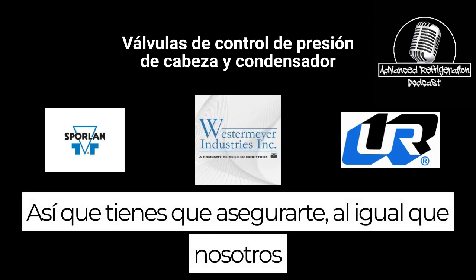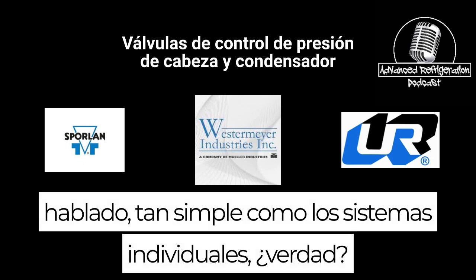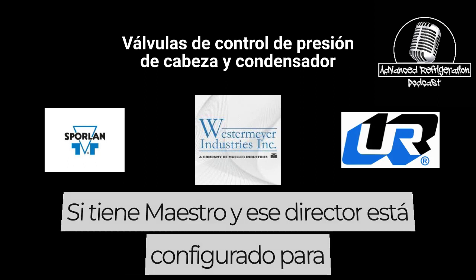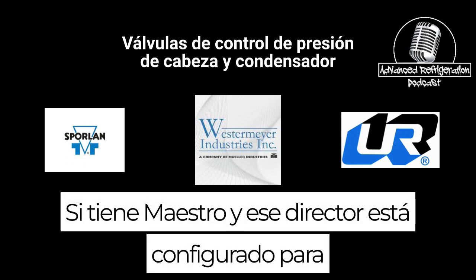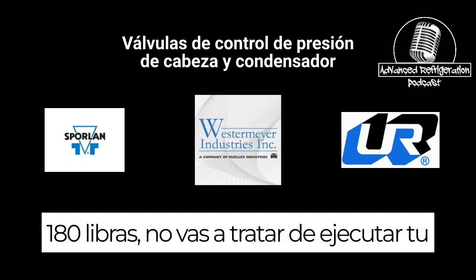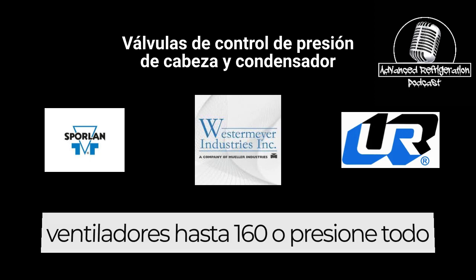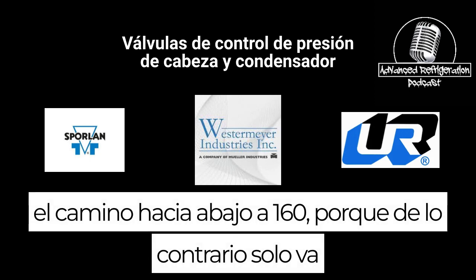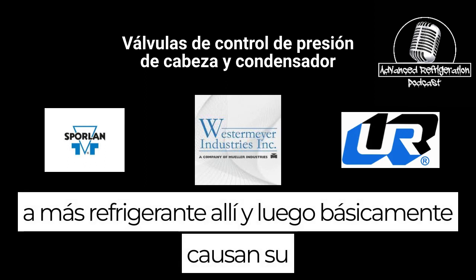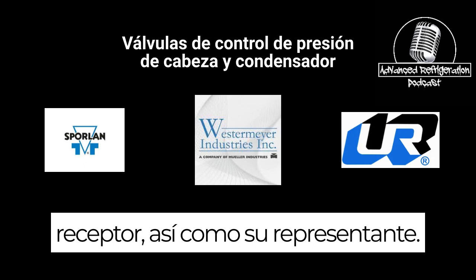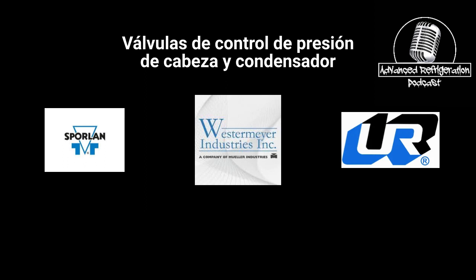So you have to make sure, just like we talked about, even on something as simple as single systems. If you have a headmaster set for 180 pounds, you're not going to try to run your fans or your pressure all the way down to 160, because otherwise it's just going to back more refrigerant into the condenser and cause your receiver, as well as your rack, to start having problems.